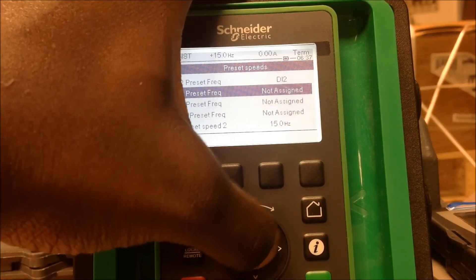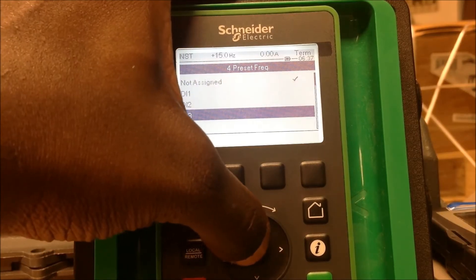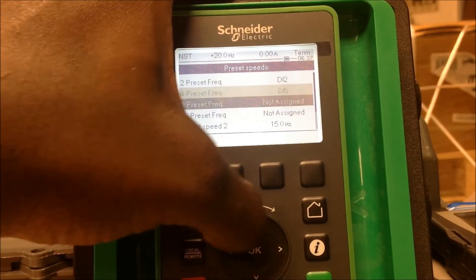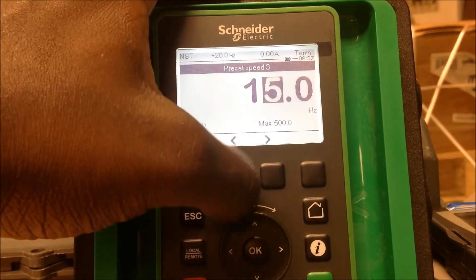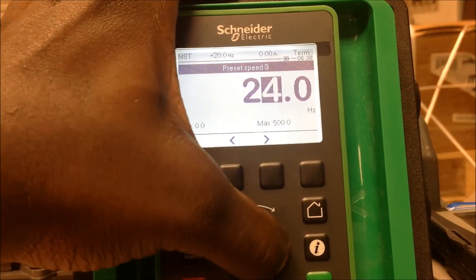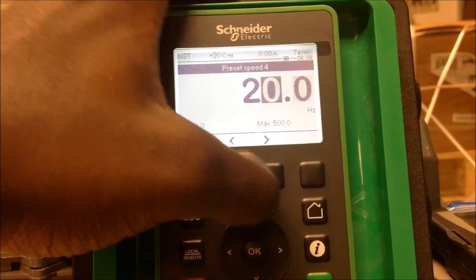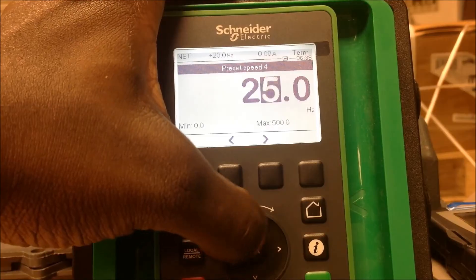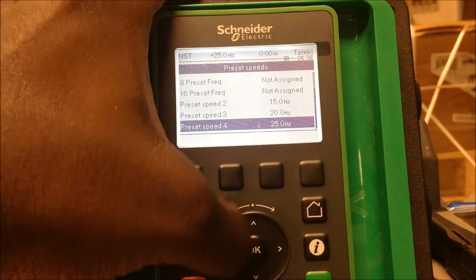Now let's say I wanted to go up to a third speed. I would come here, hit enter, and use another input — let's use DI3 for this example. That's going to give me up to four preset speeds. So now I can assign this to 20 hertz and then assign this to 25 hertz, or whatever speed you want to work with. As you can see, I now have up to four preset speeds and could go further up to eight and up to 16.